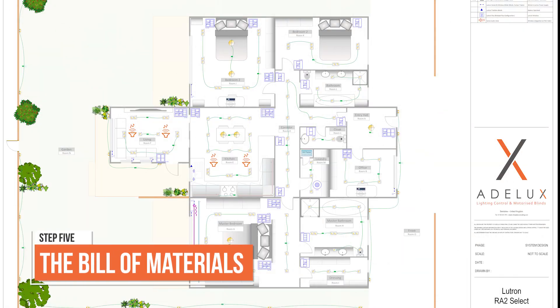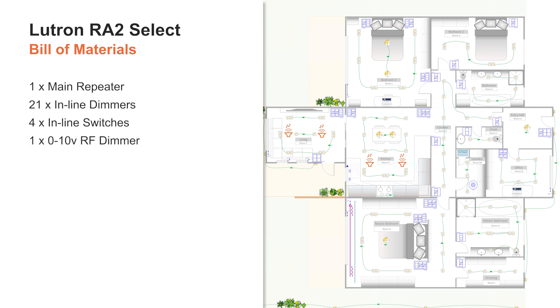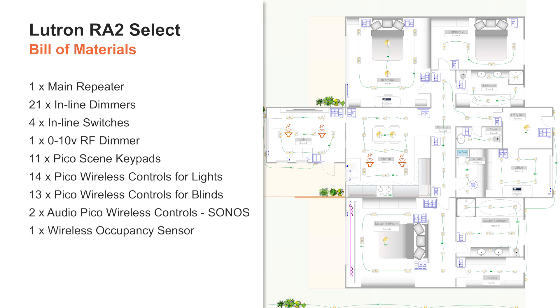Now let's put the bill of materials together — or what I like to call the shopping list. For this project I need: one main repeater, 21 inline dimmers for mains dimmable lighting circuits, 4 inline switches for non-dimmable lighting circuits, 1 0-10V RF dimmer for 0-10V lighting circuits, 11 Pico Scene keypads, 14 Pico wireless controls for lights, 13 Pico wireless controls for blinds, 2 audio Pico wireless controls for Sonos, 1 occupancy sensor, and 8 Lutron motorized blinds.